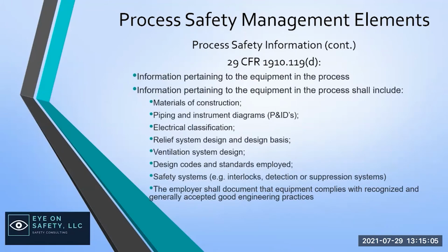We talked about the incident that happened in Glendale and their scrubber failed. And one of the key components when we get to the next part, mechanical integrity, and we'll get to that, but they talk about doing your inspections and ensuring that your equipment is operating correctly and within the parameters that it's designed for. And so you can see that even at that process in Glendale, they actually had an issue with that scrubber, which ultimately resulted in a release of chlorine.